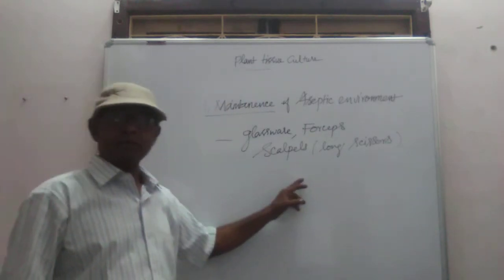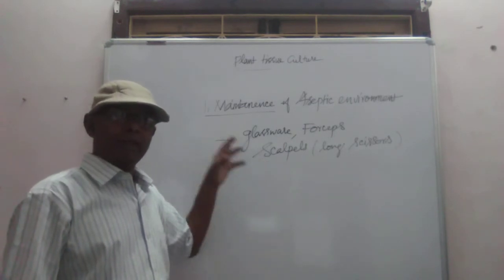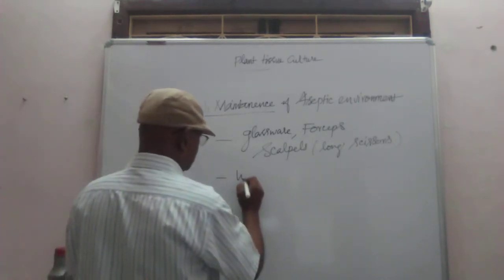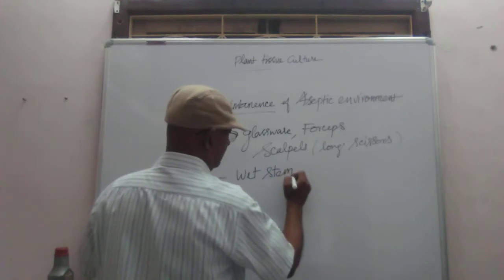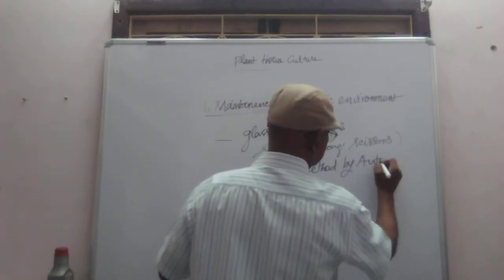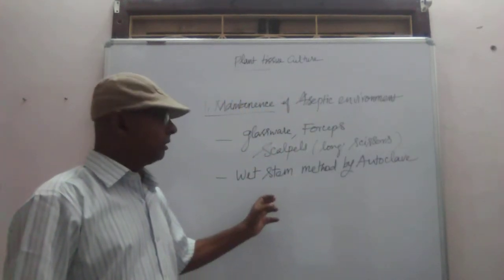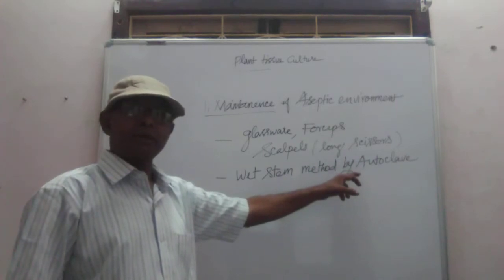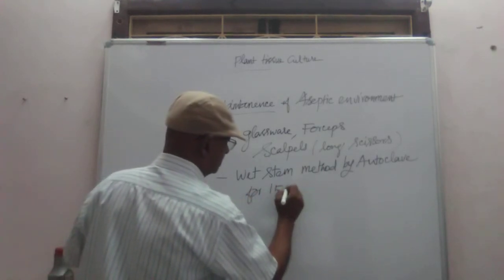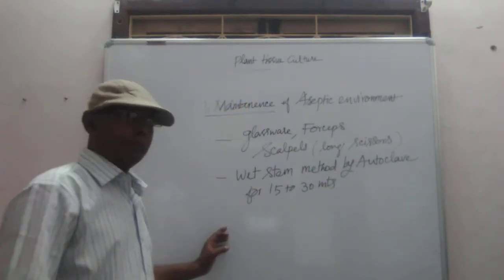These all accessories are sterilized by wet steam method by autoclave. Autoclave is an apparatus used to sterilize the material. In the autoclave, for about 15 to 30 minutes, the material should be kept in 15 psi.